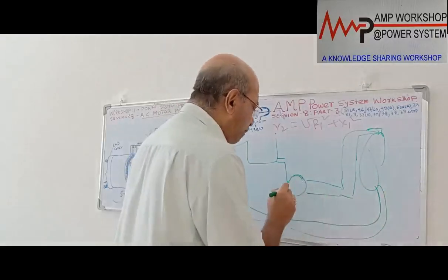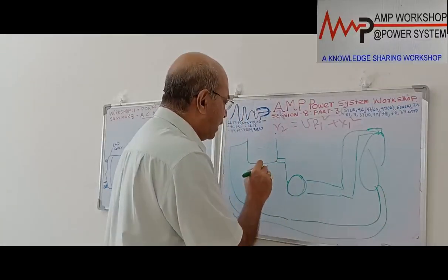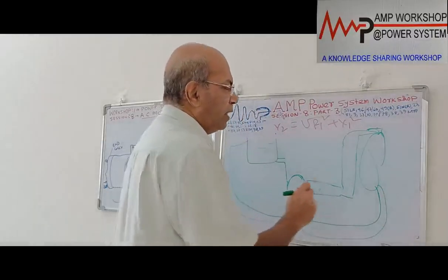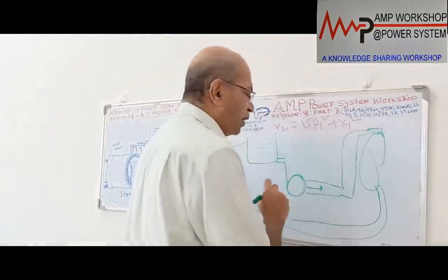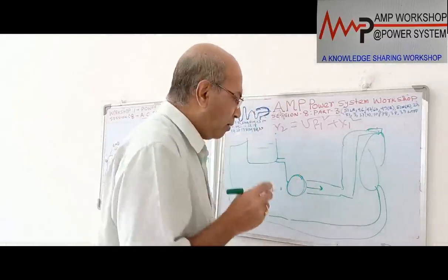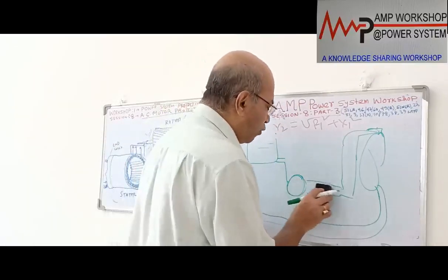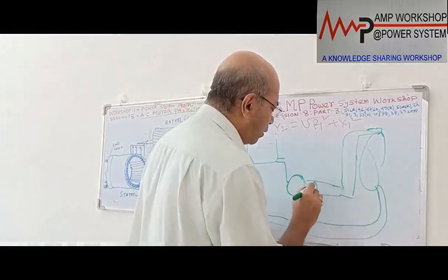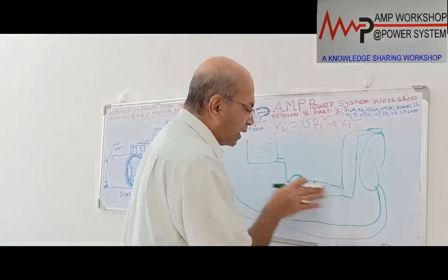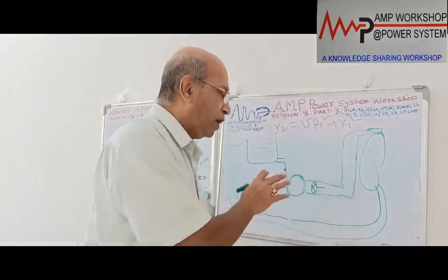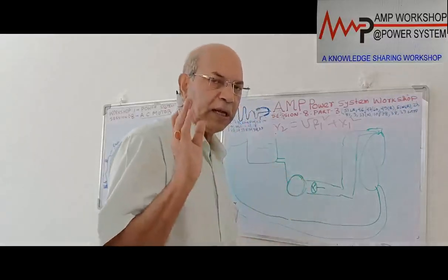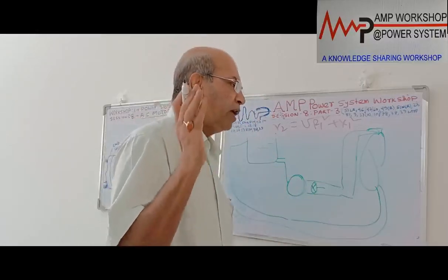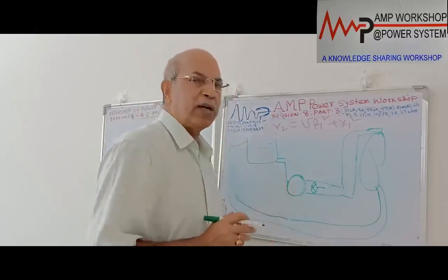Now if this pump fails, or the water leaked, in that case enough flow will not be there. So here also we do the same thing; we put a flow switch over here to measure how much water flow is going. If the flow is not adequate for any reason, then immediately the flow switch will give the signal, and with the signal with the timer we take it to the alarm, or we can take the trip.